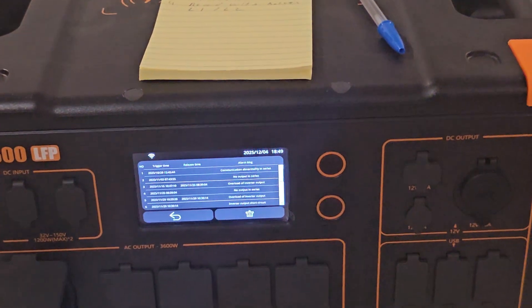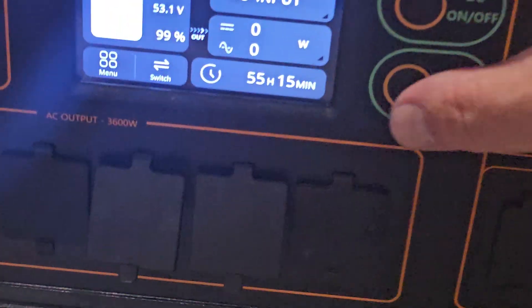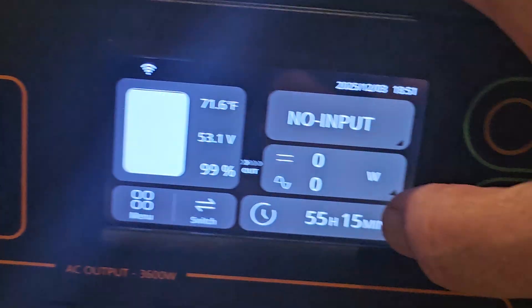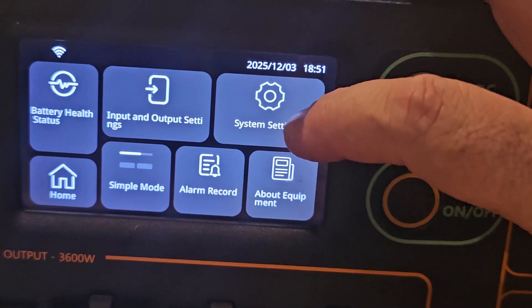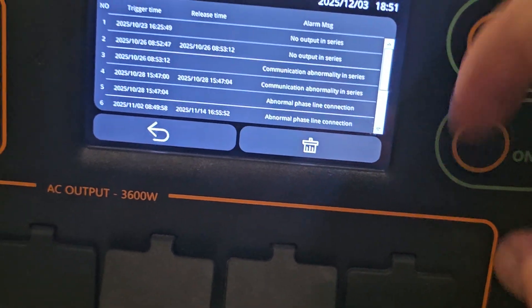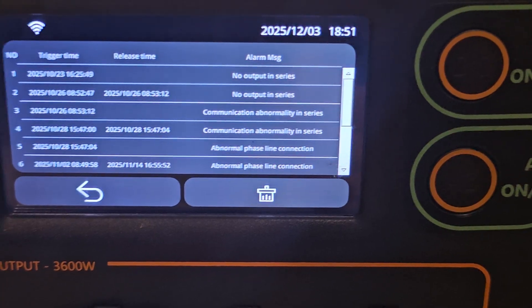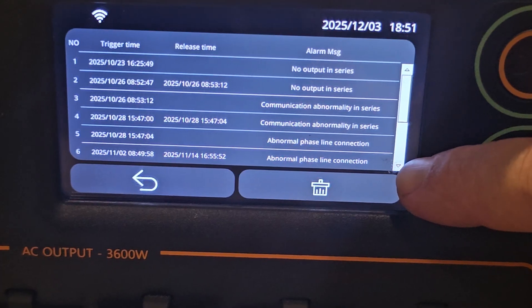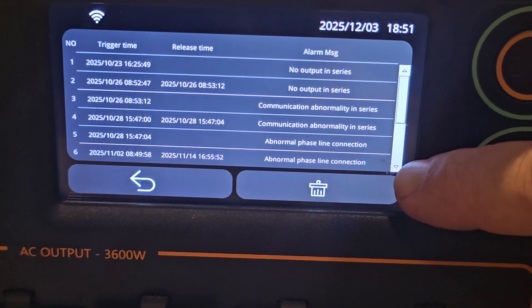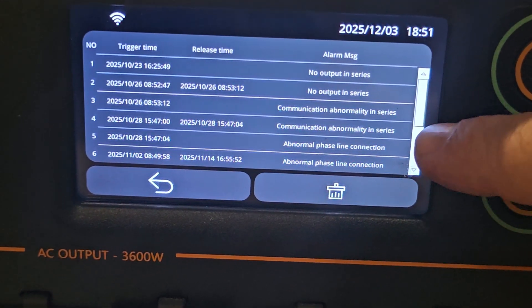I know what the overload of inverter output was — that was when a well pump and my water heater started simultaneously. We'll go over to this unit. We're going to go into the alarm record on this one, and you can see the abnormal phase line connection. That was 11-2, and 11-14 has some abnormal phase connections.